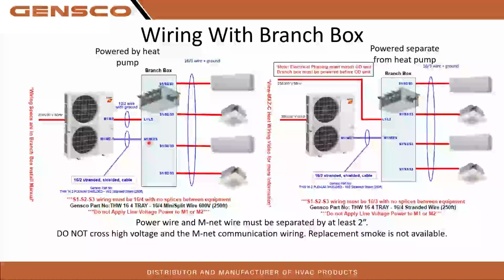Another thing I do want to add, just brought up another good point, is if you are doing multiple branch boxes, you are going to daisy chain this wire from your heat pump to your first branch box, and then from your first branch box straight on over to your second branch box. Same thing with your power wire. We don't want to run all those wires back to the heat pump. We just want them daisy chained from one unit to the next. Usually what I'd recommend is the shortest route possible as well. So if it's shorter to run to your downstairs branch box and then up to the attic or vice versa, whatever it may be, just go the shortest route you can.